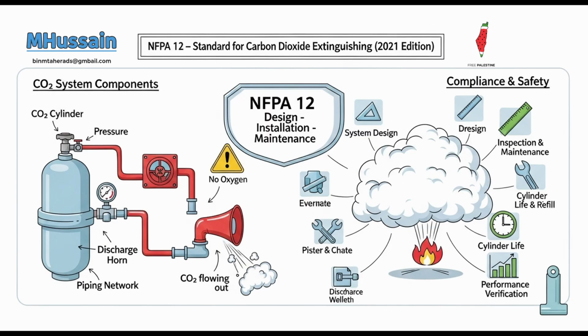Furthermore, thorough instruction and drills are required for all personnel who are within or in the vicinity of these protected areas, including maintenance or construction staff. Everyone needs drills. This is to ensure they know the correct actions to take if the system operates, how to evacuate, and what to do if a colleague is affected. Finally, ventilation is critical. Ventilation, right? Because it's heavier than air. Exactly. Means for prompt and forced ventilation of hazardous areas must be provided, as carbon dioxide is heavier than air and can collect in low-lying spaces. Without active ventilation, dangerous pockets of CO2 could linger for extended periods, creating persistent risks even after the immediate fire threat has passed. Got to clear it out properly.